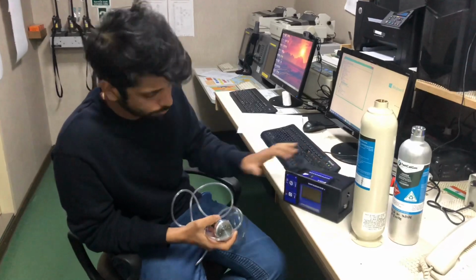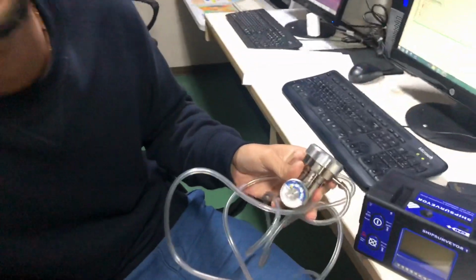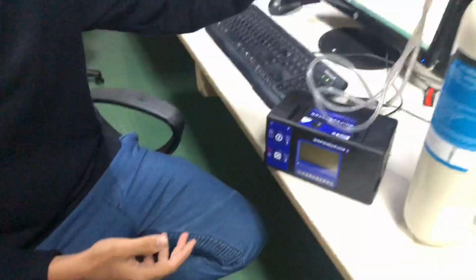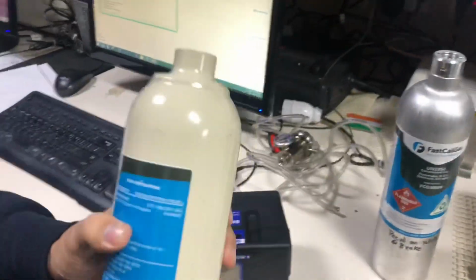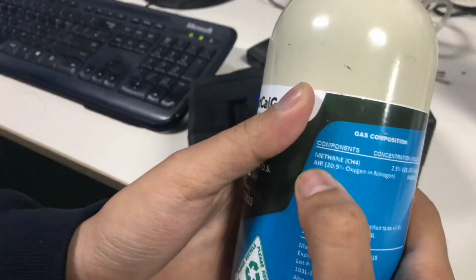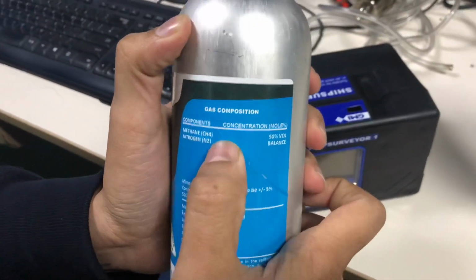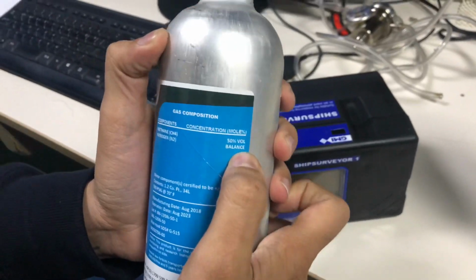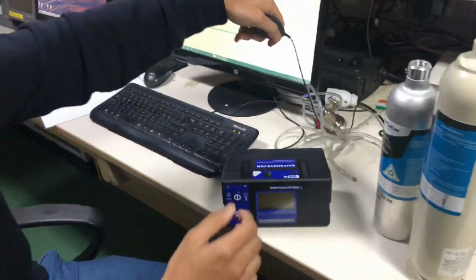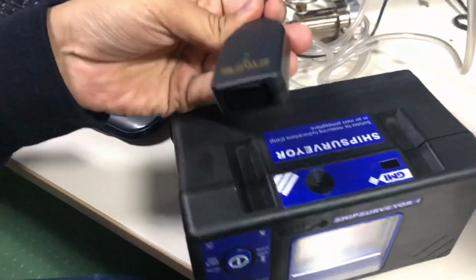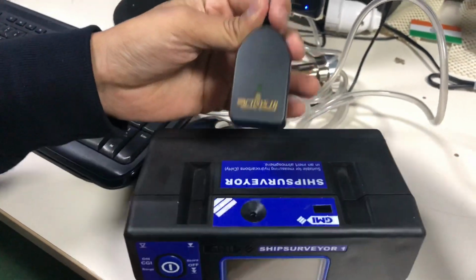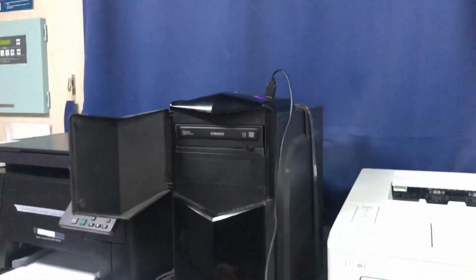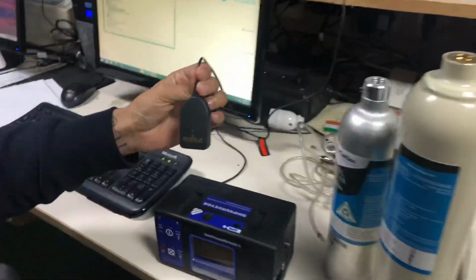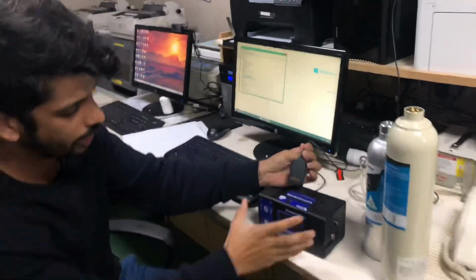So guys, for calibration of tank scope, you need a pressure regulator. This is known as a pressure regulator. Calibration gas bottles with 50% LEL methane, and a calibration gas bottle with methane content 50% by volume. And this is a universal infrared USB controller. This you have to connect to the PC. This USB universal controller is basically a means of communication between the PC and the tank scope.